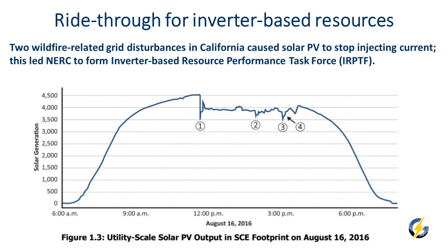This was an issue that cropped up, as you can see in the chart here, with PV generation. A few years ago in California, a wildfire event caused a large transmission line to trip, which caused a voltage disturbance across a large section of the grid. Many of the inverters at these large-scale, as well as small-scale, solar installations stopped injecting current for a relatively long period of time. You can see there were several disturbances in this chart, the resources dropped, eventually came back, but then dropped off again after additional events.